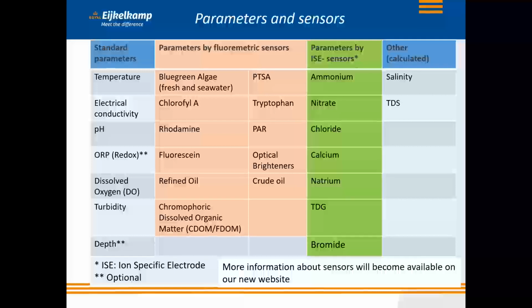Parameters that can be measured by the ISE sensors are ammonium, nitrate, chloride, calcium, natrium, total dissolved gas, and also bromide. Bromide, for instance, is a guide parameter for fertilizers. Other parameters that cannot be measured but can be calculated based on electrical conductivity are salinity and total dissolved solids. More information about our sensors will become available on our new website.